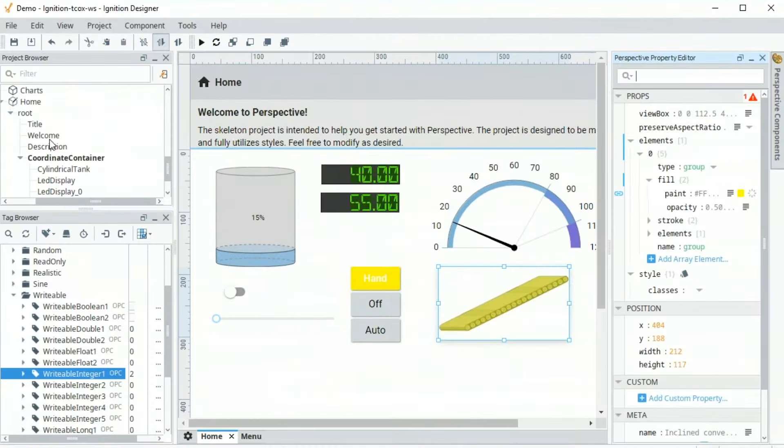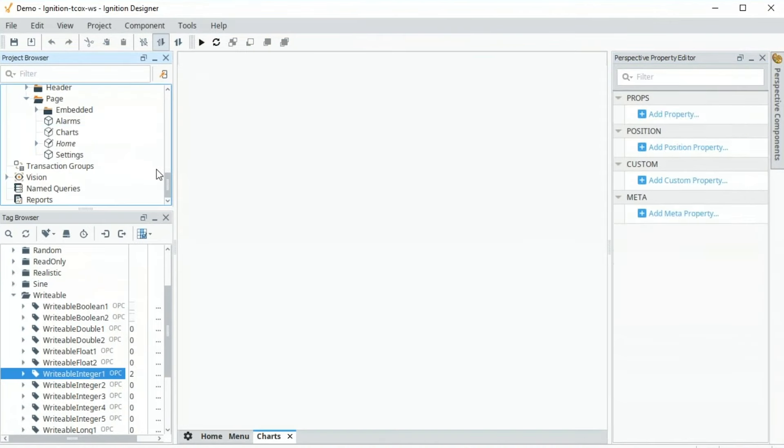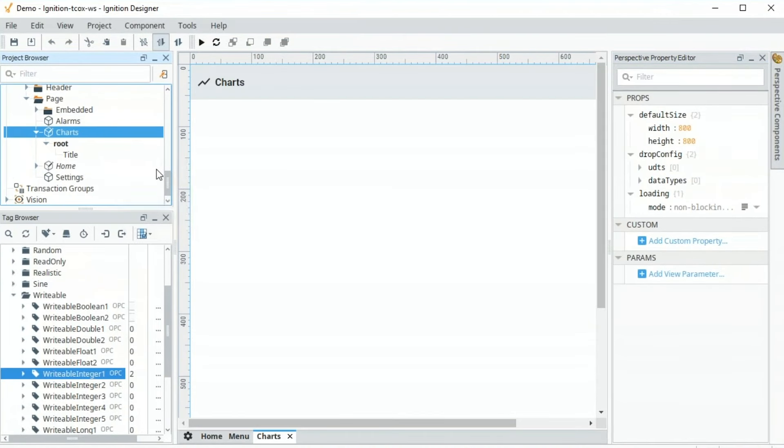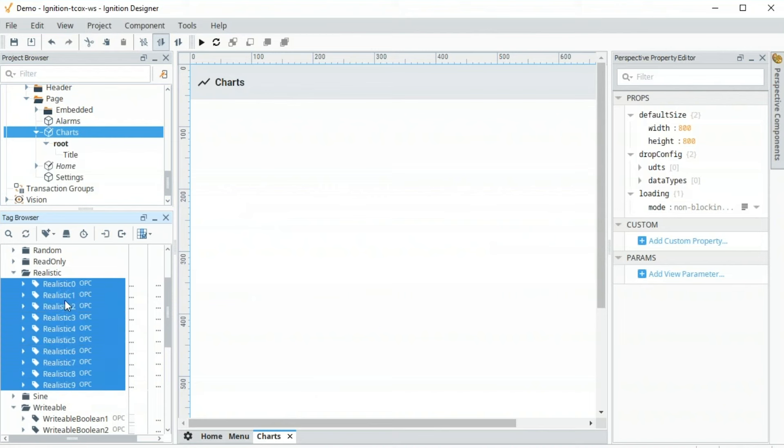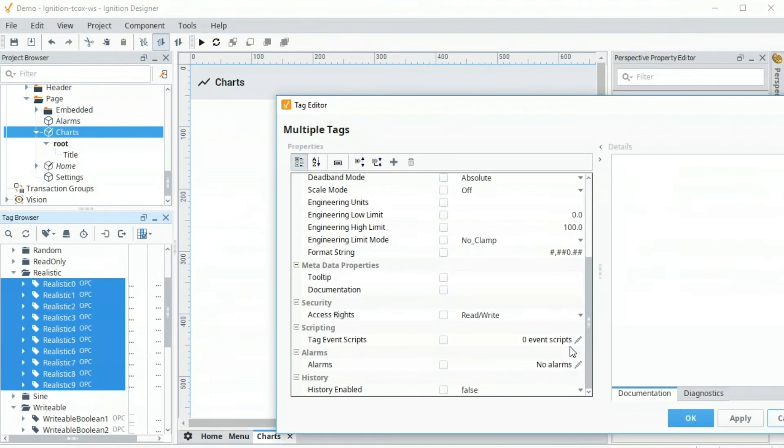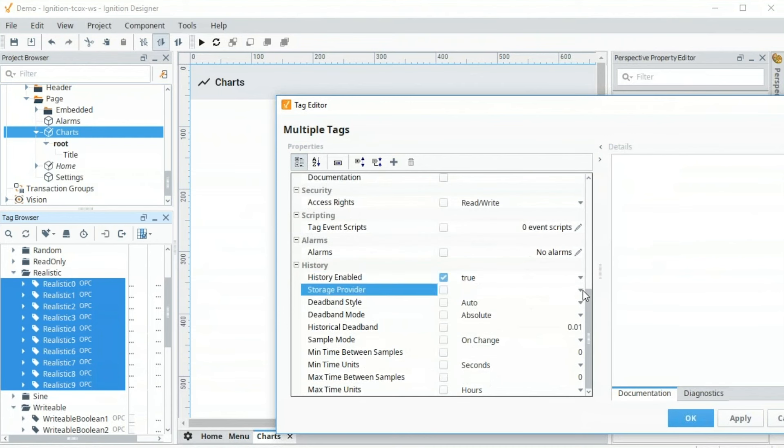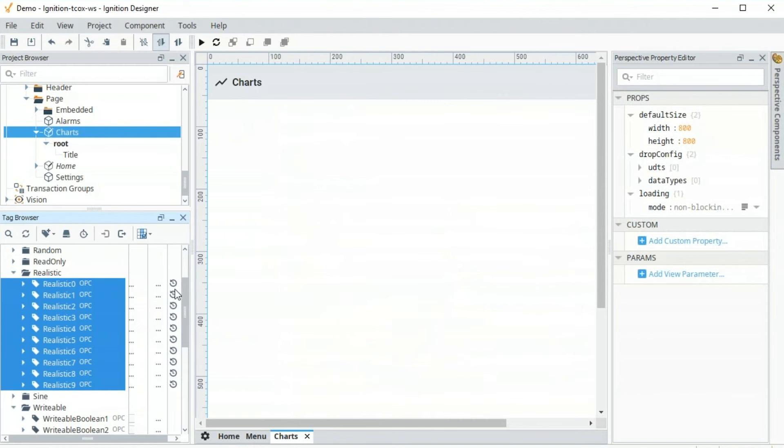Now let's show history. So let's go over here to our chart screen. And we're going to take these tags, log them to the historian, and then we're going to put a chart in the window so we can view that information. So first and foremost, we'll go to our tags. I'll select these realistic tags. Right-click, edit. We're going to go down here and turn on history and select that database that we connected up to earlier, so that DB. Go ahead and press OK. There's other settings we can go in there to tune the historian and all that.